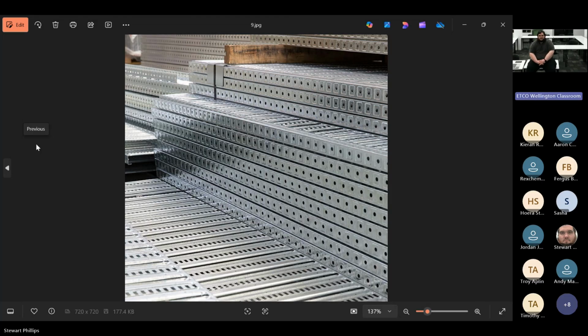You don't want your supports to be too far apart. Most of the time, if you're doing a big enough job, you'll be told how far apart to have them. But you generally don't want more than about 1.5 to 2 meters, especially if it's got a lot of cables on it. But what about environmental factors? What kind of environmental factors other than heat and ventilation do we need to worry about?